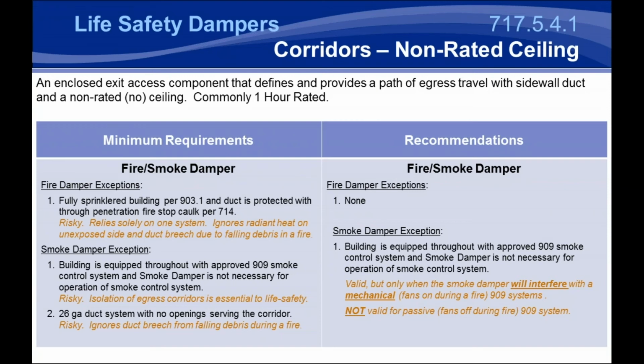So the wording's a little bit different, as they realize that it's rare that a smoke damper will impede the operation of a 909 smoke control system, because basically they're going to be tied back to the control of that smoke control system. And they're going to be opened or closed as that system dictates. So we think it's risky to remove that smoke damper requirement. As I said earlier, corridors are essential for people getting out of a building in an emergency situation.